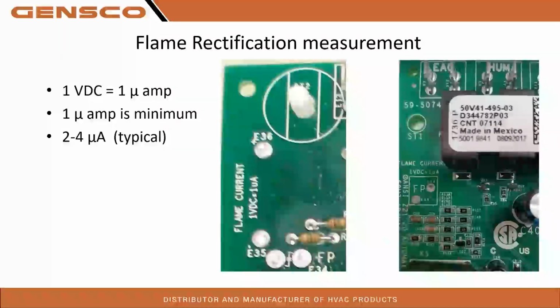Okay, so flame rectification measurement. Obviously, we've made this a little easier as time has gone on. Instead of having to rig in a wire and all that and do a meter, you can simply now take your meter and get to the flame current on the control port. So you can see here, it's actually labeled 1 volts DC with 2 little pots here. So much easier on the S series furnaces to gather that information. Okay, so remember, one is minimum, 2 to 4 is typical.